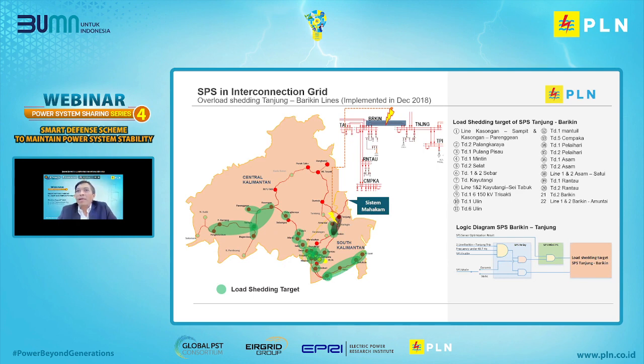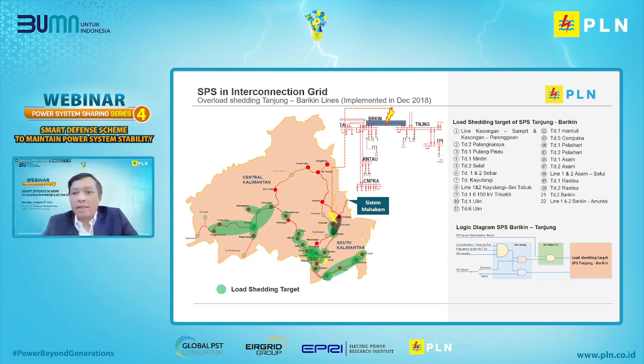Tanjung Barikin line is a backbone to transfer from North to South Kalimantan. If there is a disturbance on that line, it will cause several negative impacts to the Barito system. It can cause an overload on the South Kalimantan side, resulting in a steep decrease in frequency and voltage drop in Banjarmasin, leading to system collapse. That's why we need this.